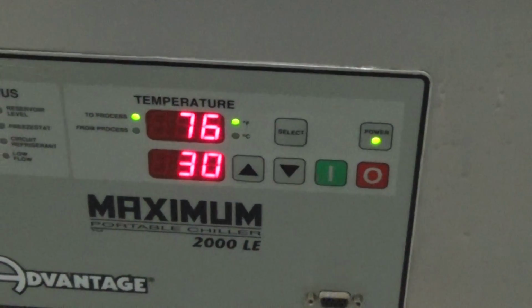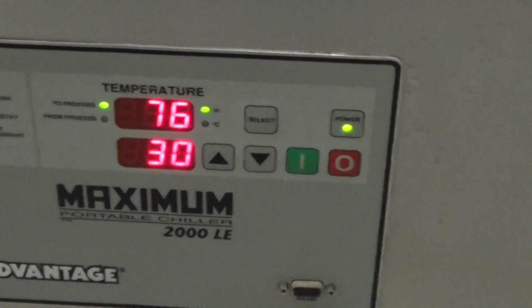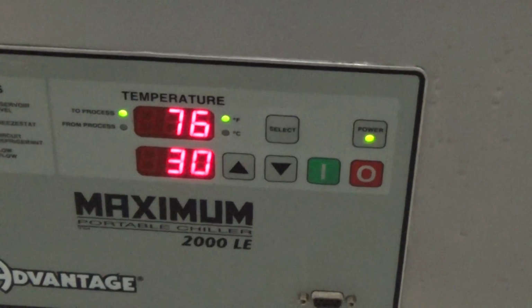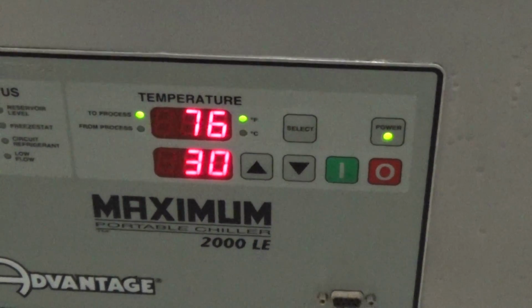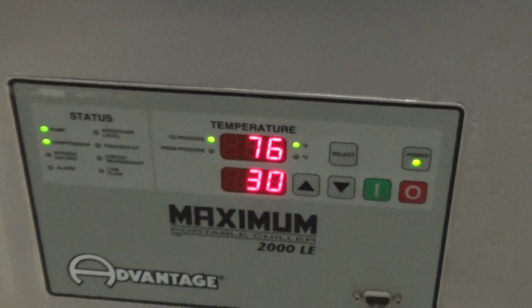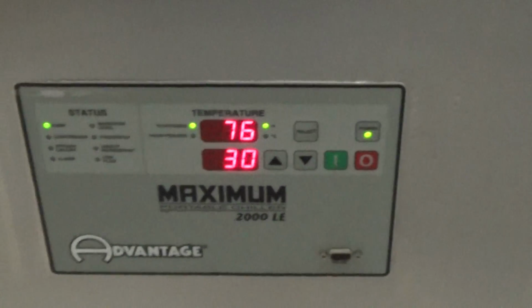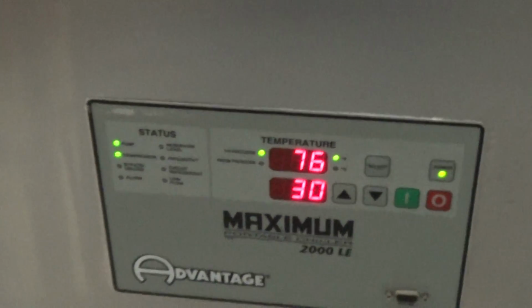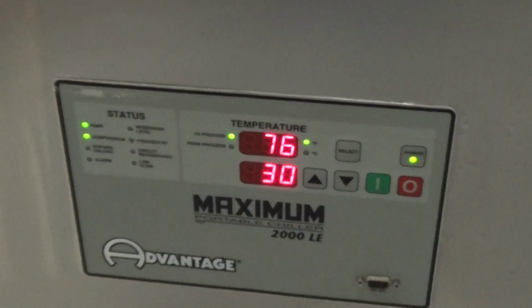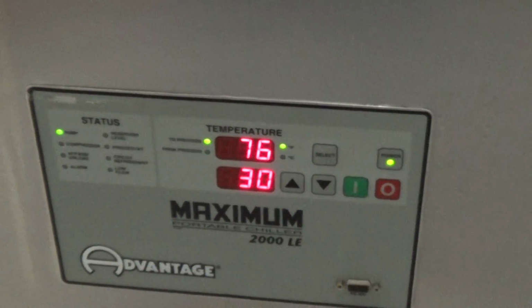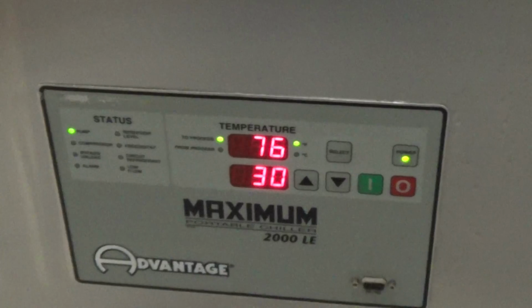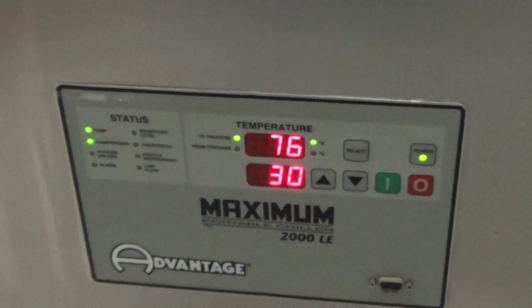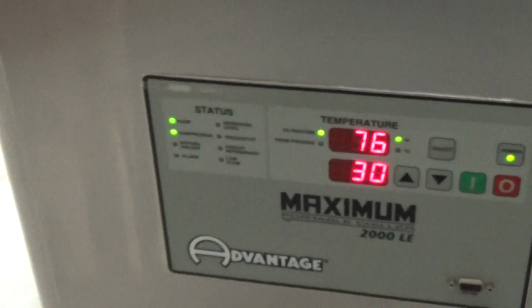On this one here, when we run it at 30, there'll be a little bit of overshoot, and it'll actually bring it down to about 26, 27 before it turns off. It will go into hot gas bypass before that happens. Hot gas bypass is when if you have less than your rated load, it's a way of keeping the compressor on longer and keeping a false load, if you will, because it's the starts and stops on a compressor that you do want to minimize.